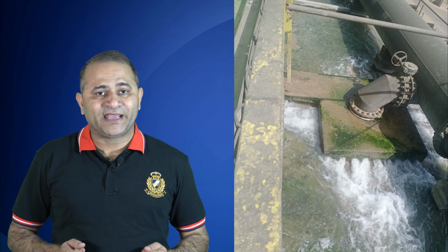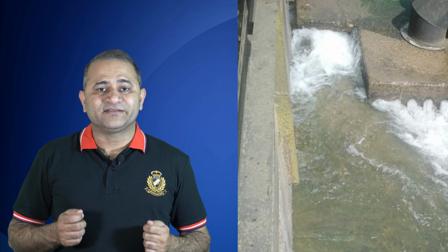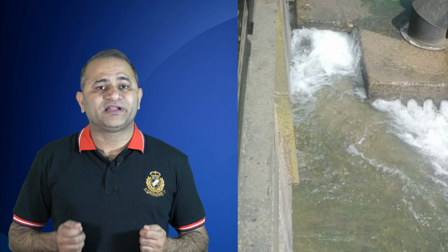It's common in open deck cooling towers that algae growth takes place despite maintaining water chemistry, because sunlight is there and sunlight is food for the algae. So it helps algae to grow in open deck cooling towers. That's why we need periodic maintenance and cleaning if we want a neat and clean surface in an open deck cooling tower system. Rapid algae growth is also called algal bloom.